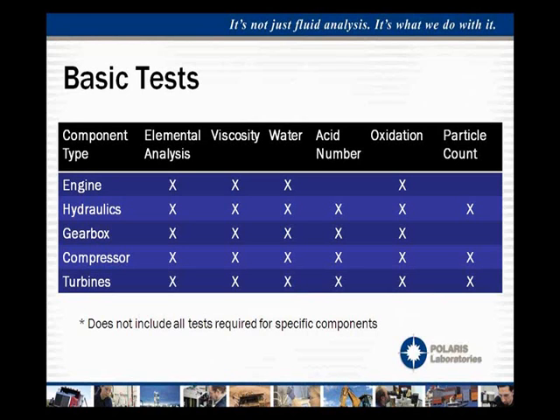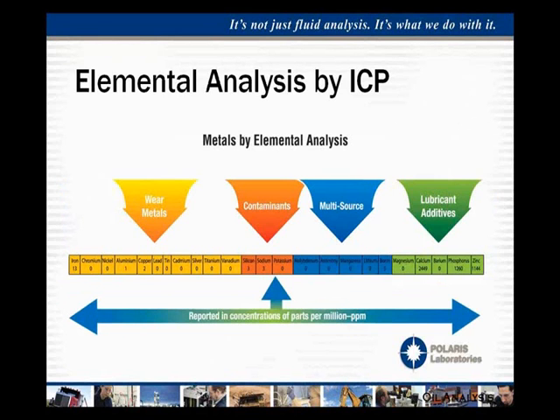Gearboxes have the same basic test package, but they do not necessarily require a particle count because gearboxes, as a function of what they are, tend to run a lot dirtier. So we don't necessarily need to know about the particles so much as we need to know more about the wear metals. Compressors require the same as hydraulics — tighter clearances and higher cleanliness requirements — and the same applies to turbines as well.